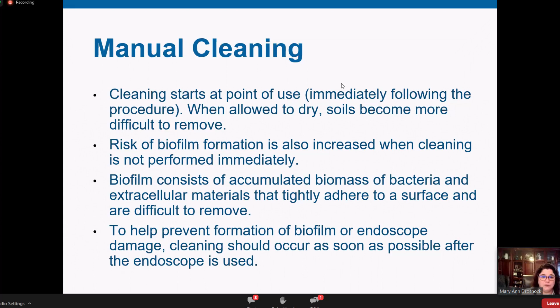The manual cleaning process, we recommend that you follow the IFU for the endoscope model that's being used, making sure we're using proper cleaning solutions, those are our detergents, and proper accessories. I still see facilities that aren't using things like the air-water channel cleaning adapter, or they're not doing suction and they should be doing suction. You're following the IFUs for any detergents that are used, any additional processing equipment like your automated flushing pumps that flush water, detergent, water, and air through those endoscopes. You want to follow all of the quality parameters for that and testing that.